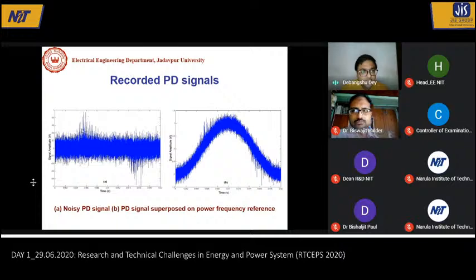If partial discharge occurs, you can see it is almost buried in noise, but there are certain high peaks, high rises here and there, that give you some idea that there may occur some partial discharges. But if you look at the real life sinusoidal waveform, it is very difficult to identify which case is a partial discharge and which case is really noise. I have magnified it, so that's why it seems to be a band of noise there.